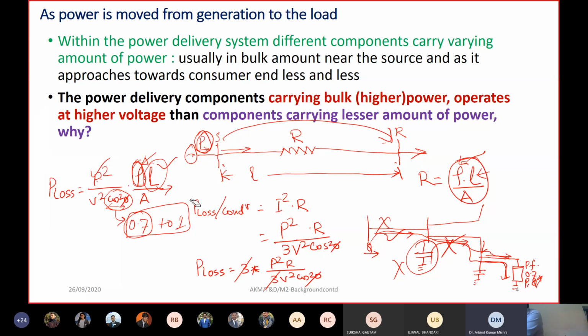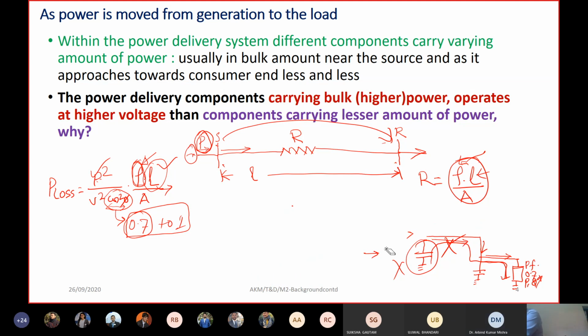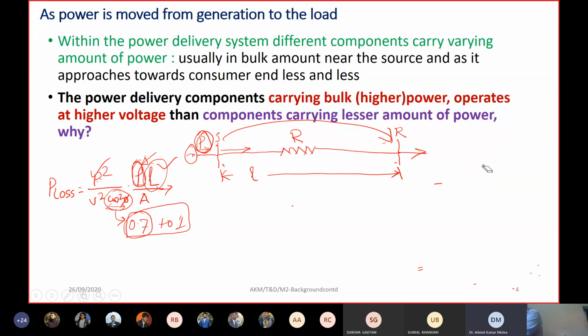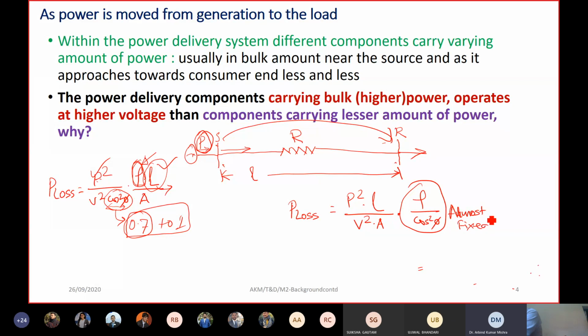So what I can summarize is that the power loss equals P squared into L, divided by V squared into A into rho, divided by cos squared phi. I've written it this way to separate the parts which are almost fixed and not varying over a wide range, whereas parameters like P and L could vary very widely.